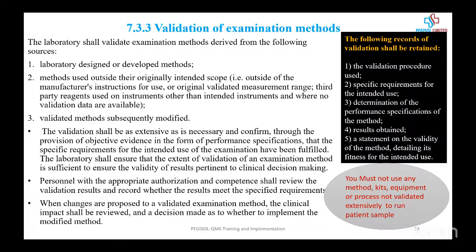I don't know if you are getting me. Let's say, for example, you have a procedure or a method that has been validated, and you're getting a new test kit. You can validate that new test kit with the already validated test kit to see if the performance of that test kit actually meets the requirement before you use it for patients.